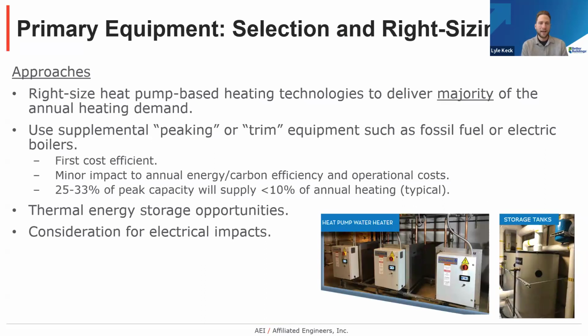And lastly, I would be remiss not to mention consideration for electrical impacts, as we're putting a lot of the heating system now away from fossil fuels onto electric. Existing electric service size, even some limitations beyond the building, from the substation level or beyond, become very real when you start considering these things. So balancing the electric resistance that you're using with heat pump or fossil fuels to minimize that electrical impact. And often what you'll see is that the peak electrical demand gets shifted from the summer cooling months more towards the winter heating months with a building that is fully electrified.